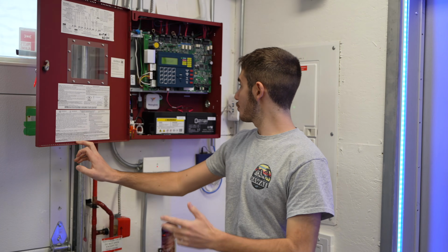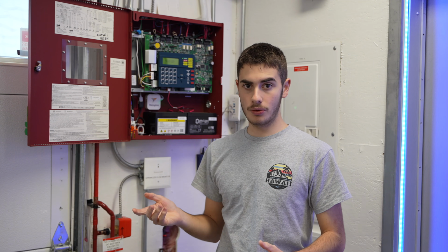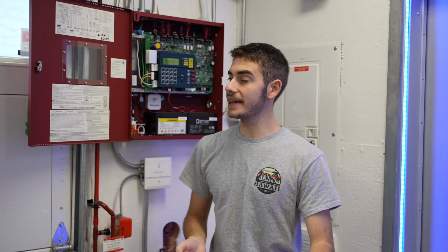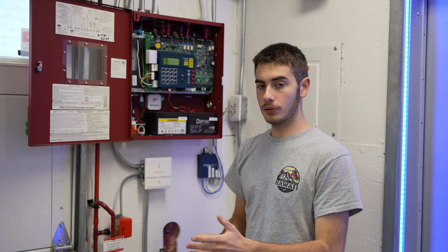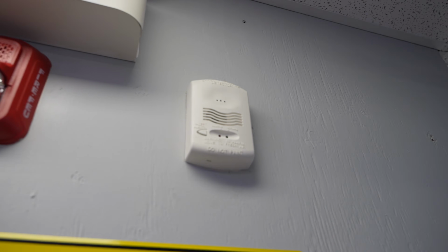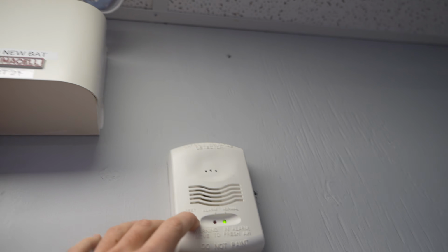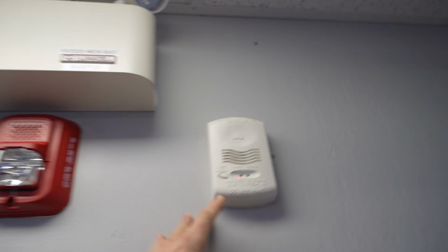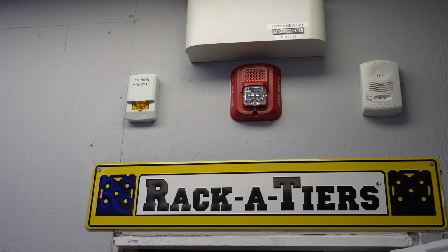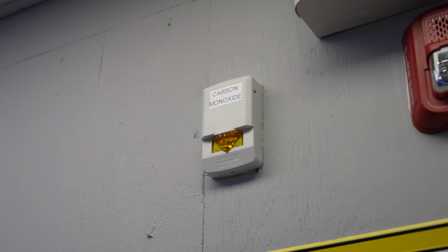Oh, I was trying to make a demonstration there that when I hit the drill button, both the horn strobes and CO strobes go off, which was the issue I was trying to fix. And what I was told is I need to set that control module to non-silenceable. I haven't messed with this since the last video that I know of. Okay, let's take a look into programming here. First, let's see if this even still works the way it's supposed to by setting this off. Yup. So it's doing what it should.